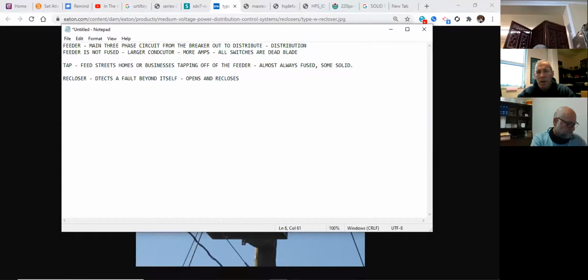Does this sound like a circuit breaker? It's very close to what a circuit breaker does, but it doesn't have all that extra technology inside of it. They're all typically going to be instantaneous opens. Instantaneous open, wait, then close. Instantaneous, if the fault remains, instantaneous wait, reclose. Wait a little bit, instantaneous fault, open, and reclose. That's all it does, it doesn't do the I and the T. It just detects faults beyond itself, and of course, it's programmable.